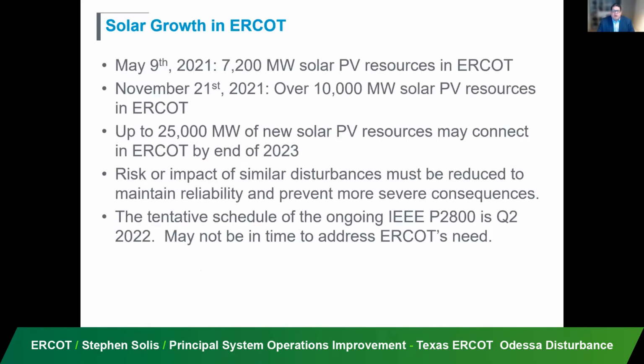To talk about the growth in ERCOT, why we're concerned. At the time of the event, we had about 7,200 megawatts of solar PV resources in ERCOT. This has grown quite dramatically within the last year. Right now, we have over 10,000. So we've had almost 3,000 megawatts of solar interconnect within the last 6 months. When we're looking out to the end of 2023, potentially up to 25,000 megawatts of new solar PV resources may be connected. So obviously, if you have a risk, you lost about 1,000 out of 7,200, 15 to 20%.